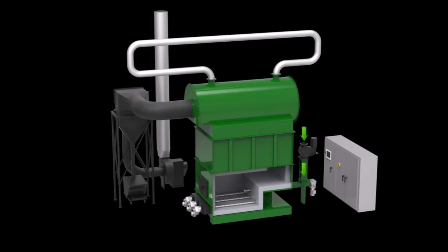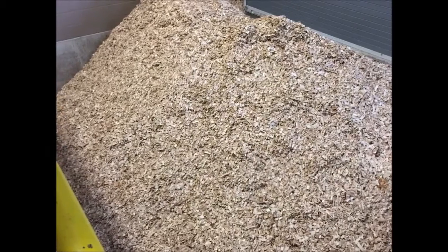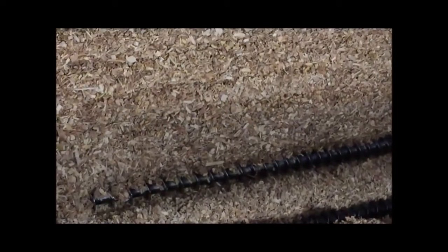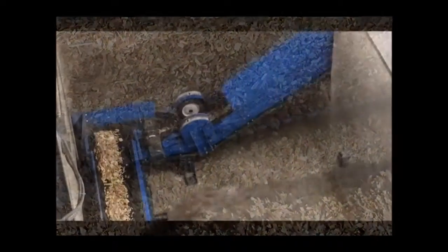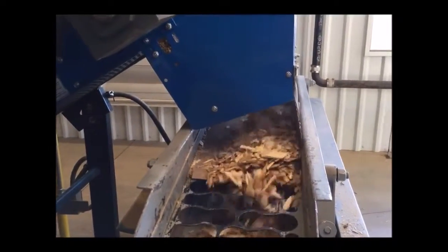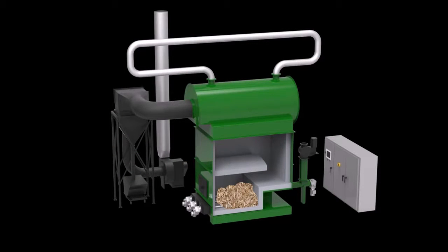Here, we can see the wood chip fuel being delivered into the combustion chamber and drawn towards the combustion area. A major characteristic of the combustor is its fuel feeding mechanism, built with large containers where the biomass fuel, often wood chips, is deposited by truck. From here, it is fed by auger, which we can see operating here, and also by conveyor belt, which delivers the fuel to a table where it is sorted by size and finally inserted into the end of the combustor, all automatically. Finally, in the combustion chamber, it is moved by the augers through the combustion area, ensuring complete combustion.